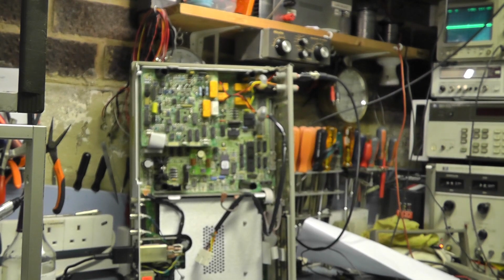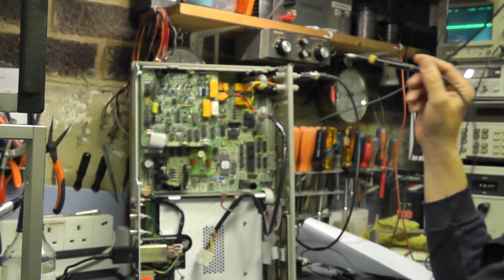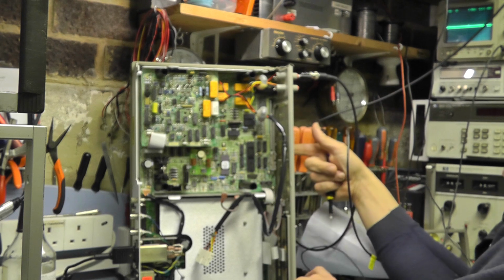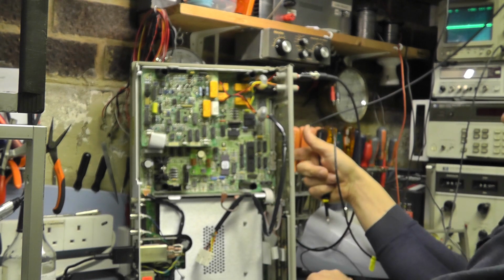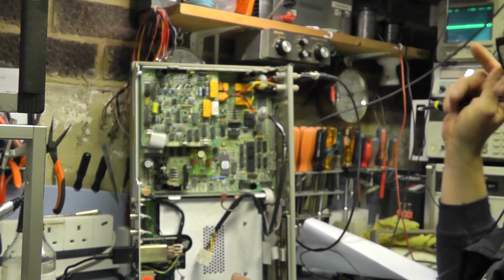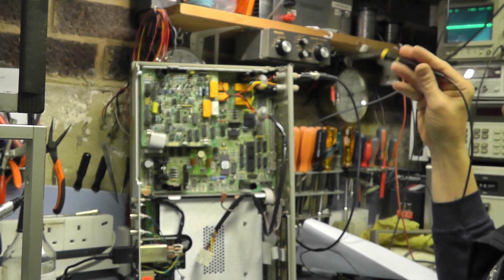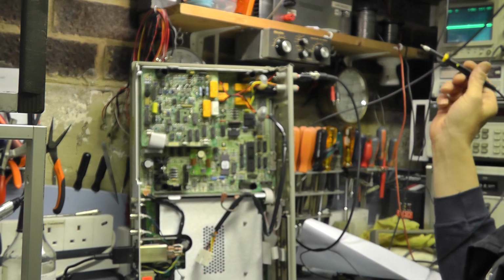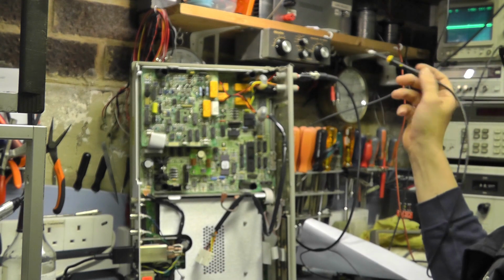Right, we've ascertained that there's clearly something wrong with the AC section of it. If I've got this unit on AC and I feed in, say, a 10 volt signal, I'm getting something like 10 millivolts through. Hence why it's failing its self-calibration. There's no signal getting through.